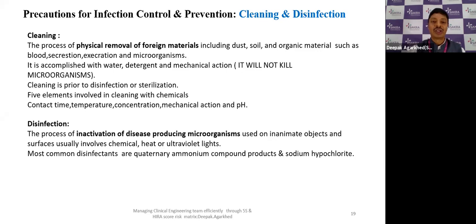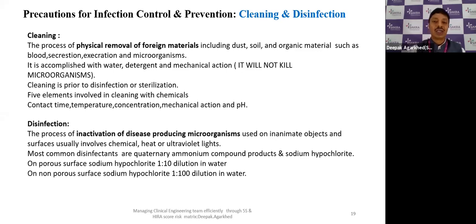Most common disinfectants are quaternary ammonium compound products or sodium hypochlorite. As per CDC guidelines, for a porous surface, sodium hypochlorite in 1:10 dilution with water is used. For a non-porous surface, sodium hypochlorite in 1:100 dilution with water is preferred.